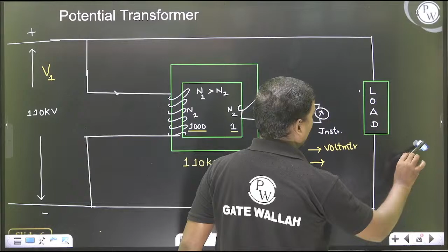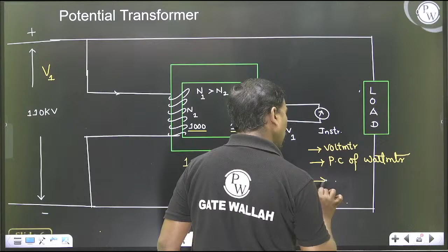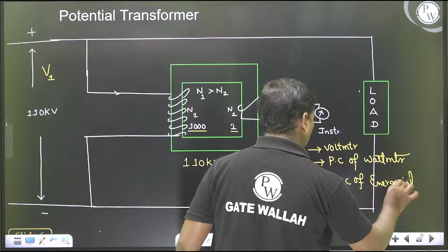The potential transformer is called a parallel transformer because it does not come in series. The secondary instrument connected here can be a voltmeter, using PMMC or moving iron type. You cannot use PMMC directly for AC, but you can use moving iron type, or the pressure coil of a wattmeter, or the pressure coil of an energy meter.